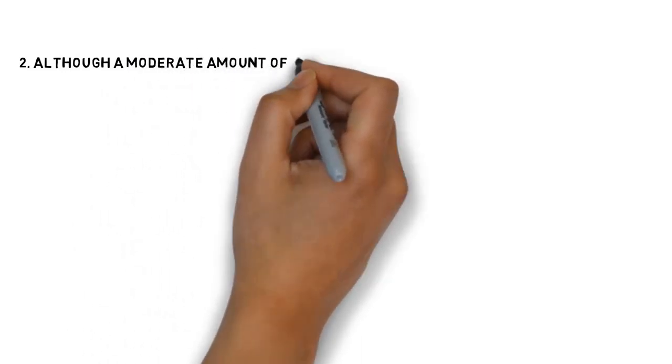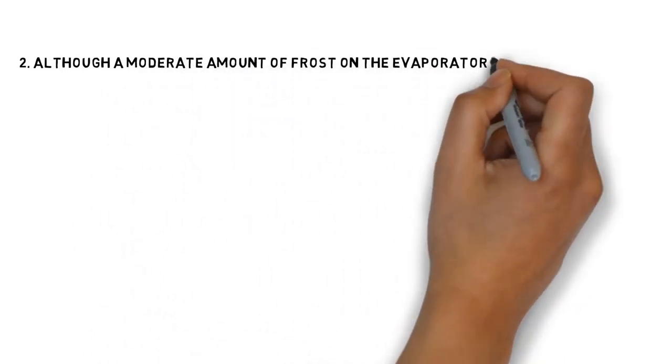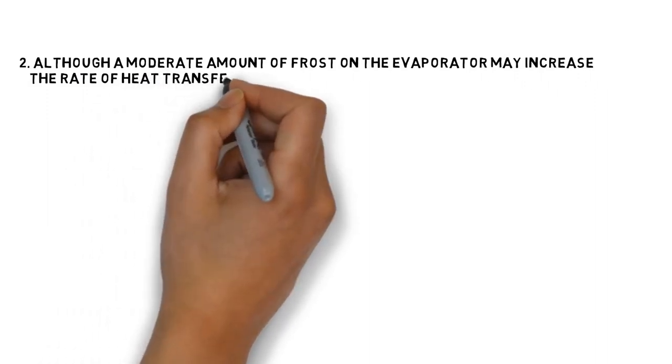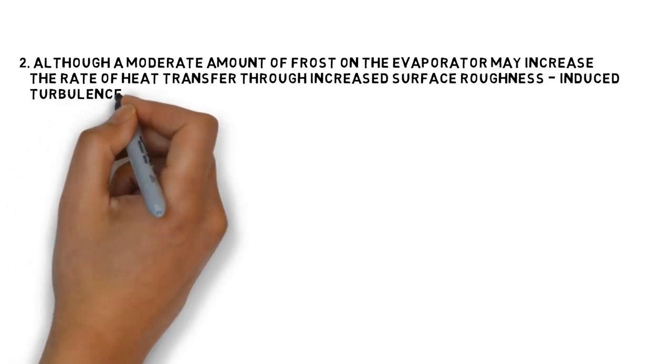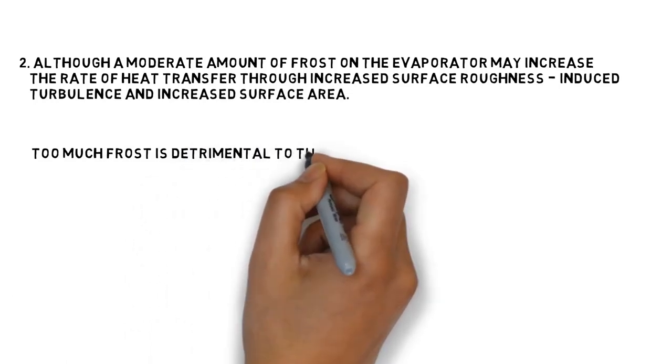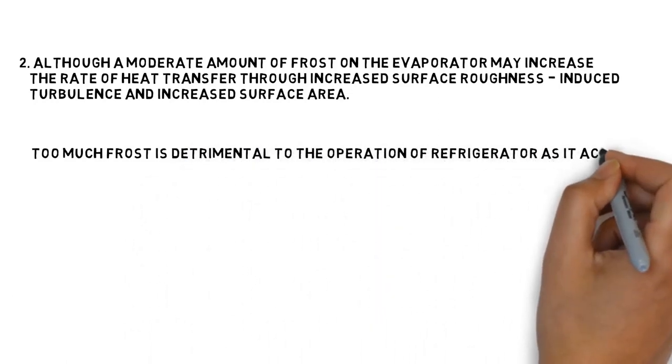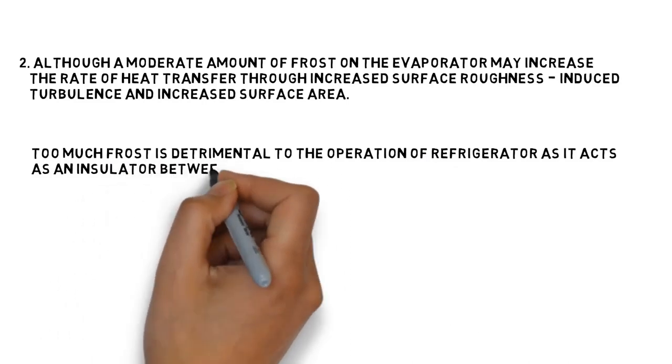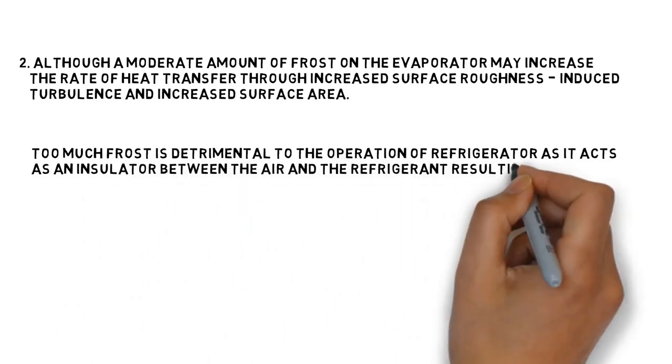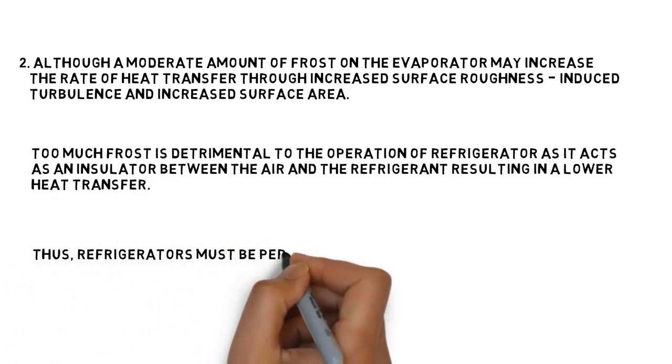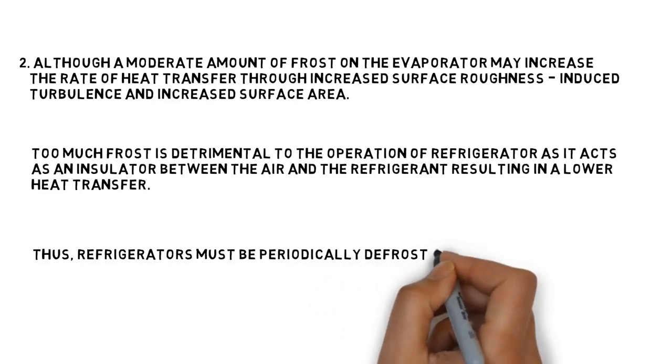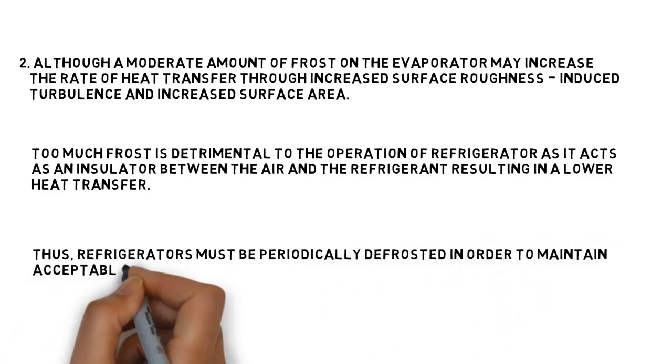Although a moderate amount of frost on the evaporator may increase the rate of heat transfer through increased surface roughness, induced turbulence, and increased surface area, too much frost is detrimental to the operation of refrigerator as it acts as an insulator between the air and the refrigerant, resulting in a lower heat transfer. Thus, refrigerators must be periodically defrosted in order to maintain acceptable efficiencies.